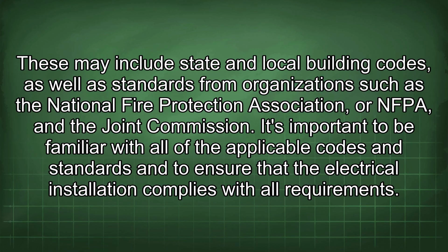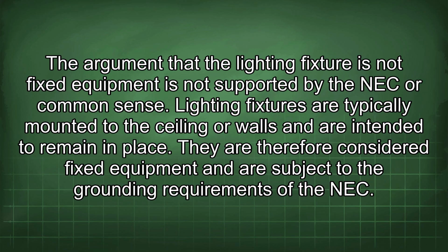The argument that the lighting fixture is not fixed equipment is not supported by the NEC or common sense. Lighting fixtures are typically mounted to the ceiling or walls and are intended to remain in place. They are therefore considered fixed equipment and are subject to the grounding requirements of the NEC.